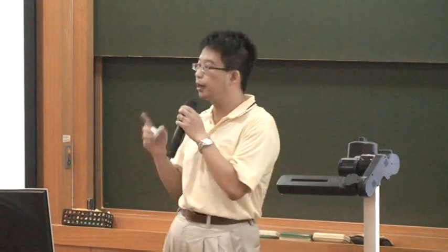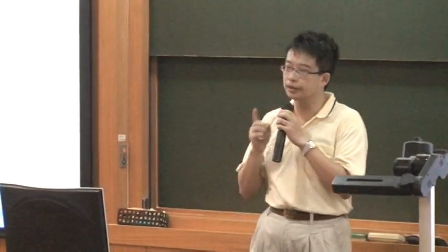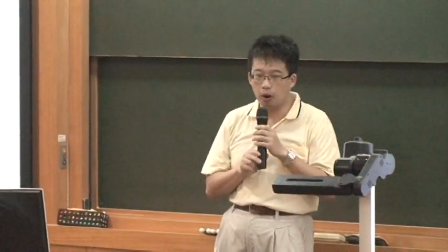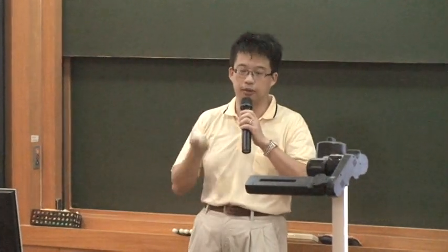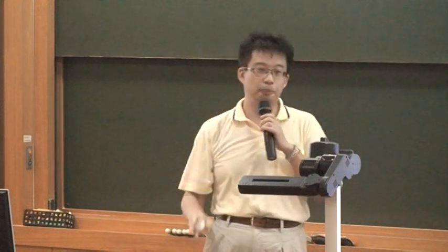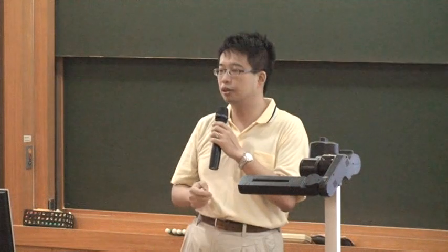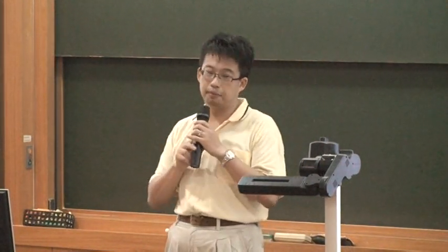So the focused ion beam not only provides you the scattering image, but actually most of the time is used to manipulate the profile down to nanoscale. So it's a machine tool. Precisely speaking, it's a milling tool. You can dig a hole or dig trenches with the focused ion beam, and you can still see the image.